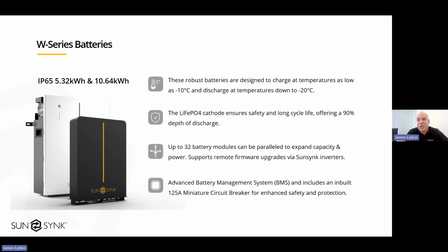There is still a level of derating as the temperatures get lower and lower, but they will still charge and discharge. LiFePO4, so really safe chemistry, and you can parallel up to 32 of the W series batteries together. Obviously, you'd never do that with a 5 kilowatt hybrid inverter, but back to what I mentioned, if you've got multiple inverters in parallel, it's really scalable on the battery storage. All of our batteries have full internal advanced BMS, and a built-in 125 amp MCB for isolation.